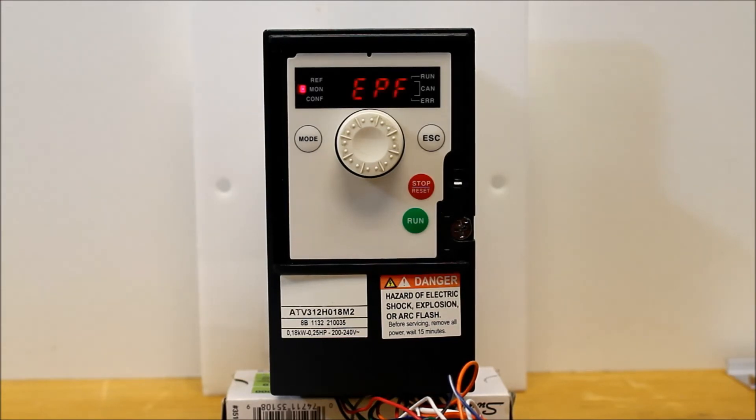As you can tell, the drive gave you an EPF fault code, which is external fault, and it stopped the drive.